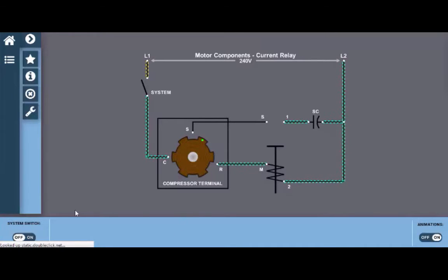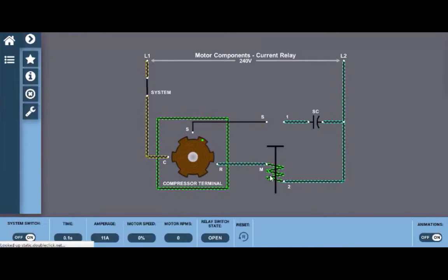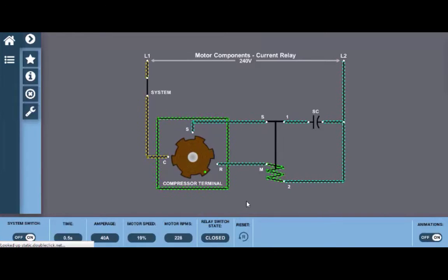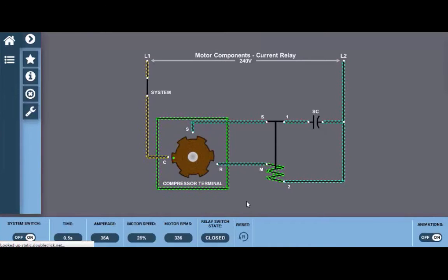So let's take a quick look at this. By turning the selector switch to the on position, we can see that we've got current flow through the coil. With the motor in the locked rotor position, the amperage is increased four to five times above the normal running amperage.